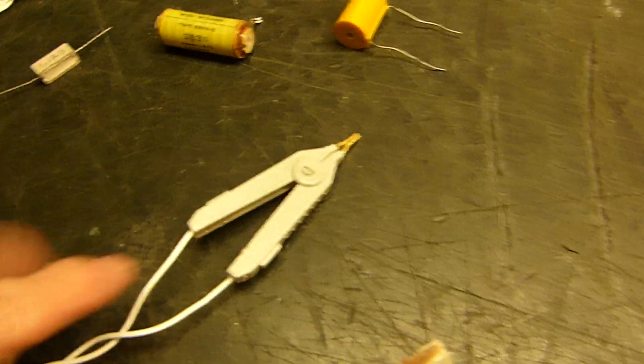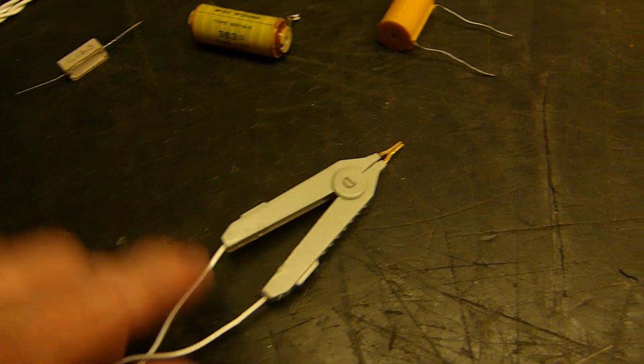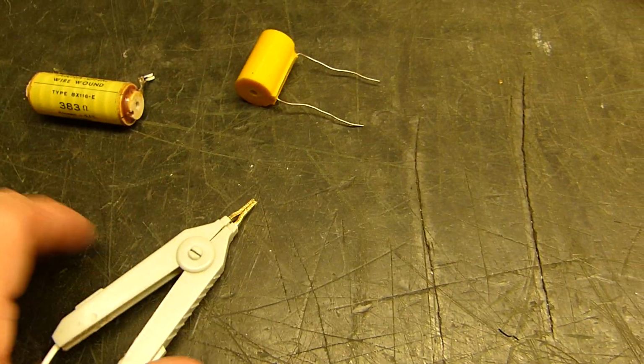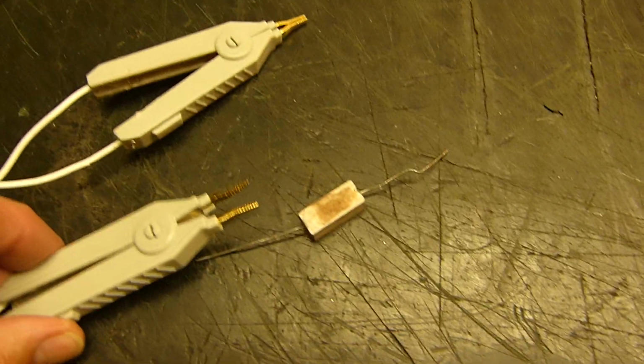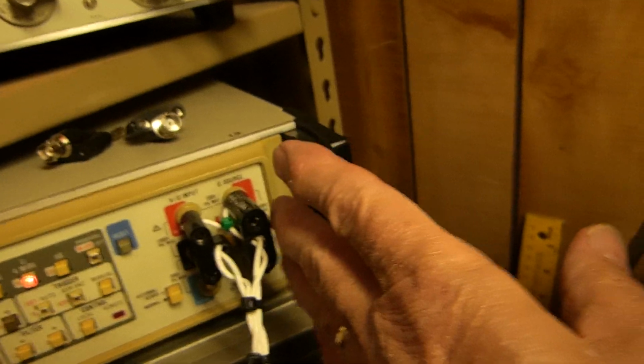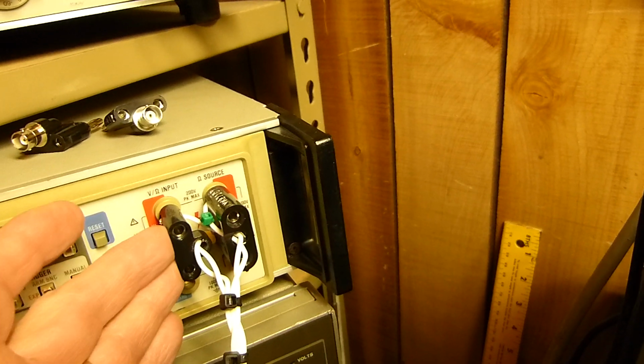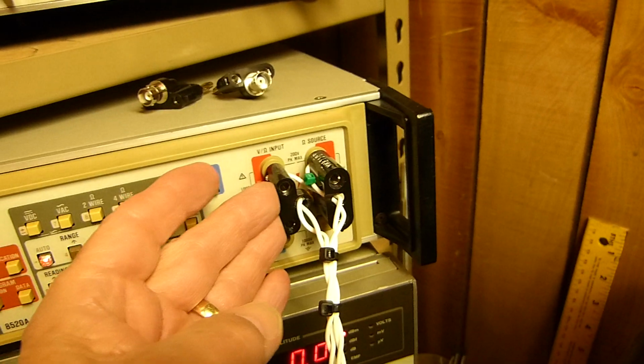And what I'm using here is these little probes right here. See, this wire and this wire are separate. They're not connected together internally. So the tips are separate. The tips are separate here too. What you do is you apply the voltage across the resistor, and then you measure across the resistor so that it eliminates the resistance in these wires.